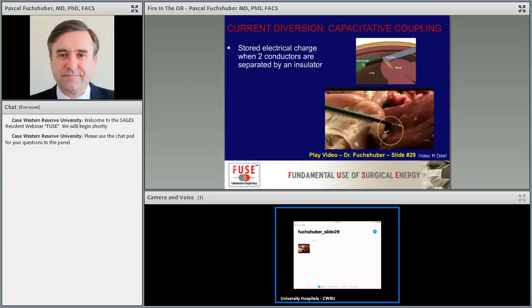And this electromagnetic field can jump to another insulated or non-insulated device, and the energy can be transferred simply by having those two instruments close together. They don't have to touch. And that's called capacitive coupling.